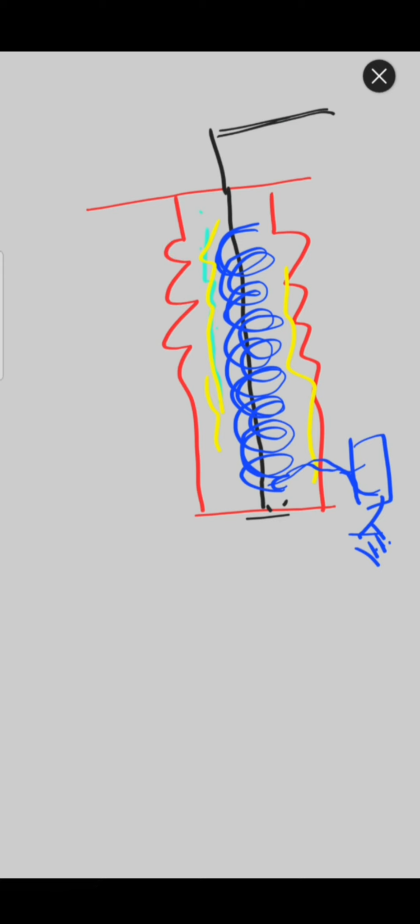Yes. So while doing tan delta, we remove this, the insulated tan delta point. This is the tan delta point. The tap is taken from inside the impregnated paper, and normally it is grounded. While doing tan delta, there is the provision on the HV side, but there is no provision from the LT side because this impregnated paper is inside the bushing.